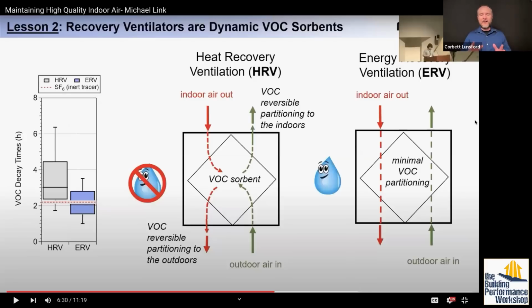So the way that an ERV or HRV works, it brings outdoor air in and brings indoor air out. Supposedly, the indoor air that we're taking out is already stale. That's why I like to exhaust them from bathrooms. The outdoor air coming in is supposedly fresh, and not like during a wildfire or some horrific pollution event. So those two streams brush against each other on the way through. In HRV cores, the air streams do not touch each other. They're touching the walls of hallways, basically. They're going by each other, and the walls then transfer energy.